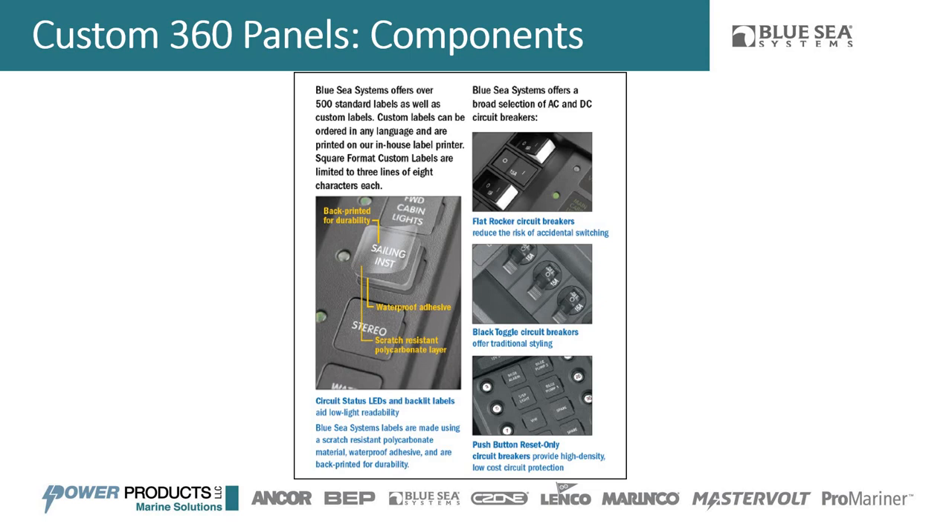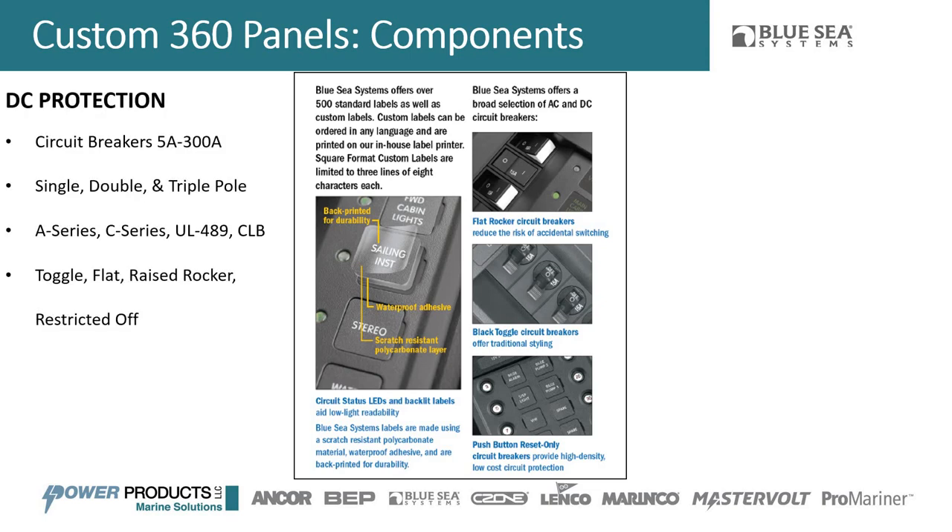We always get asked about voltages and amperages. We have DC and AC options, and you can design a panel with mixed DC and AC in the same panel. We have circuit breakers from 5 amps to 300 amps — single, double, and triple pole. We have A series and C series breakers, UL-489 breakers, and CLB breakers which are push-to-reset. We have toggle circuit breakers in multiple colors — white, black, and red — and flat rocker breakers so you won't accidentally toggle them since they're recessed and flat.